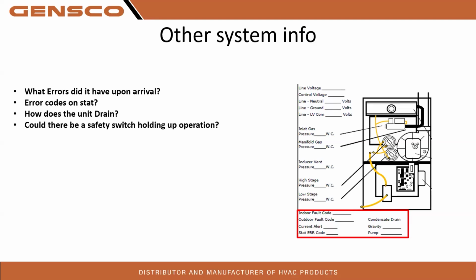Of course, how does the unit drain? We need to know, is it a gravity, is it a pump? Do we have a safety switch maybe with a pump that's interrupting, breaking our call? It's good data to know, right? So could there be a safety switch holding operation? Maybe even a wet switch sitting in a pan. Maybe the furnace is in a pan because of its location and it has a wet switch. Write it down: wet switch installed. And maybe how that wet switch breaks. Wet switch breaks red. Wet switch breaks yellow. Whatever that looks like. So the more data you put down, the better off everybody is.